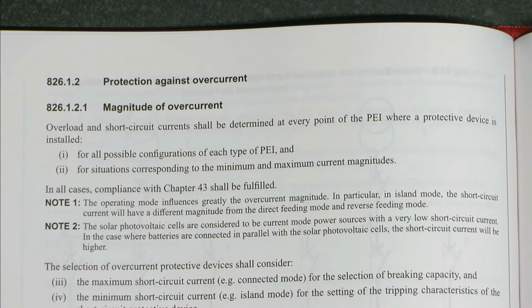The other thing to consider is, if you're then running from your batteries and inverter, what kind of characteristics does that supply have? It's not going to be anything like the grid at all. Grid supply typically has high current availability - if you short-circuit it, you'll get a very high fault current. But if you have an inverter, its actual short-circuit current could be incredibly low.